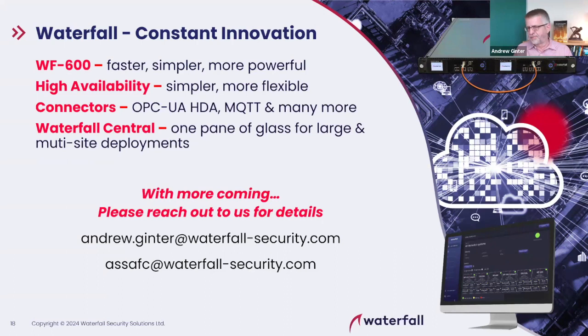That's all you can ask for. And so if we update the firmware, or something changes, where there's some sort of gap for 5 minutes in the enterprise historian, DA cannot fill it in, whereas HDA has the backfill capability. HDA will let you fill in those gaps. This is why people might have deployed DA in the past, because it was the obvious thing to deploy.